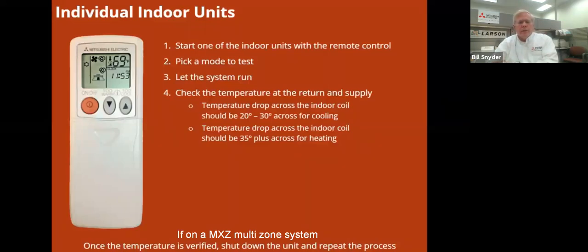Just put this in here to tell you on a multi-zone unit, this is just a reminder for me, on a multi-zone unit, when you're starting them up, it's easy to get them cross-wired because you get all those wires from inside going outside. It's good if you would tape the wires or wire tie the wires to the line set when you run them so you don't mix them up. But a good thing to do on day one is when you start up the unit, start them one at a time. Start up unit A and just verify that it's cooling. Then start unit B up, or the second unit, go back to A and shut it off. Then you don't have any time delays. And just verify each one is cooling one at a time.